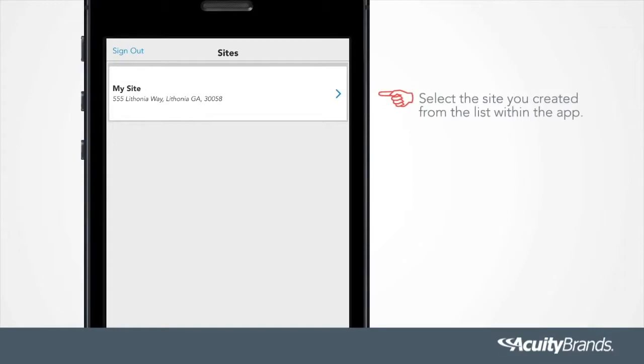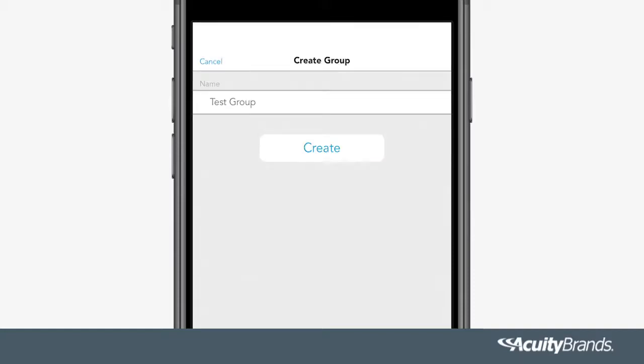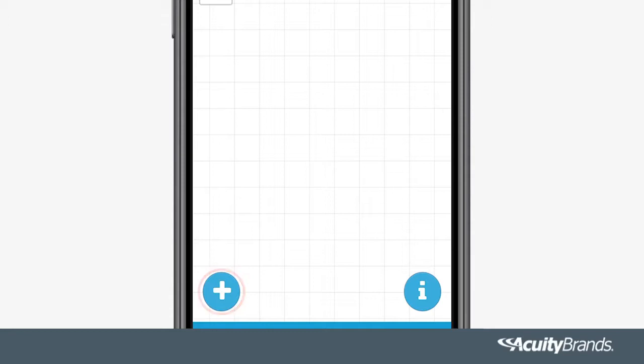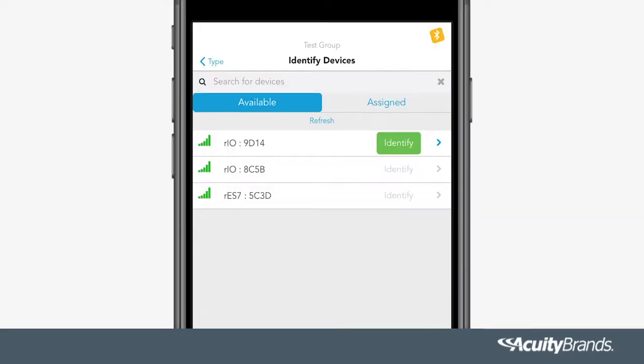Select the site you created from the list within the app. Press the site you want to start up, then press Groups. Press the plus button or select an already existing group. Type your group name and press Create. Select the group you have created. Now identify the devices you would like to add to the group by tapping Devices, then press the plus sign. Select outputs, sensors, or switches to begin adding devices to your group. Press the identify button and the device you have selected will begin to flash. Select the arrow next to the identify button to add the device to your group. This must be done for all devices being added to a group.